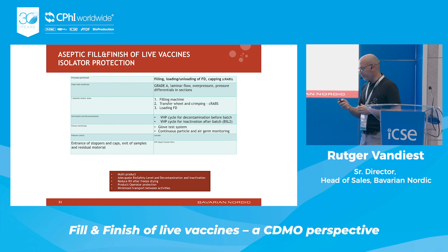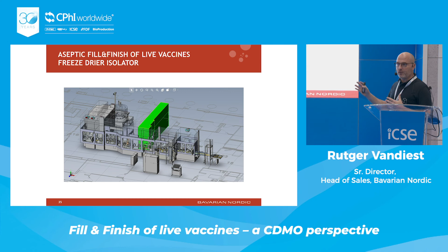Important for us, it's a multi-product isolator. For instance, if we have one product running for 5 days in the freeze dryer, we still can add another product on the filling line. Adequate biosafety level and decontamination and inactivation thanks to the isolator and the VHP cycles. We can reduce relative humidity after freeze drying, product and operator protection, and of course there are minimized transport steps between the different activities. So this is, for instance, the isolator part after the depyrogenation tunnel. Next, you see the isolator that goes to the freeze dryer. And it means, like I said earlier, if you have a product in the freeze dryer, we still can run the line for a liquid product.